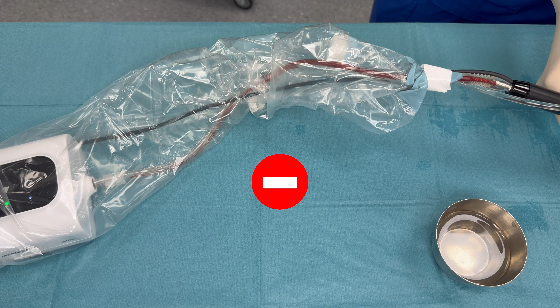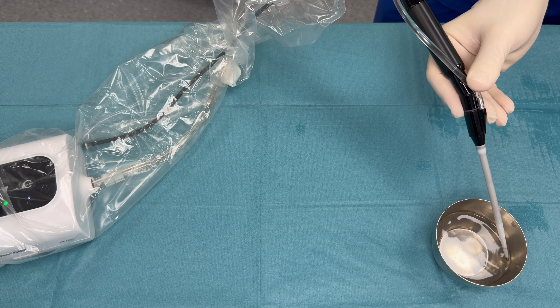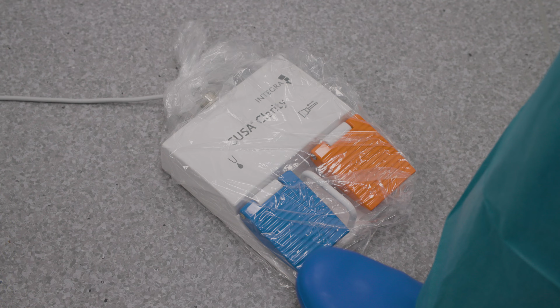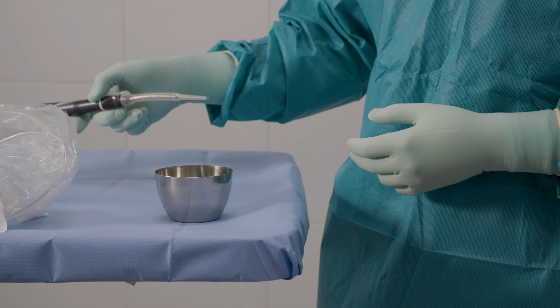Tissue stuck in the tubing may cause delayed detection, and excessive blood in the tubing may reduce the sensitivity of the device. The following practices help minimize these risks and ensure optimal performance. Use the flush pedal frequently to clear blood from the tubing and ensure the tubing remains clear. When the surgeon is not using the handpiece, the scrub nurse aspirates fluid to keep the tubing clear.